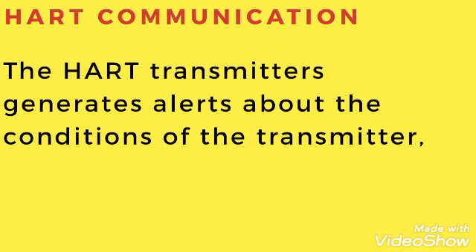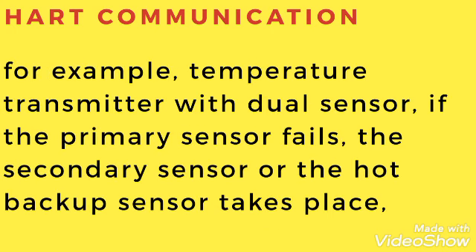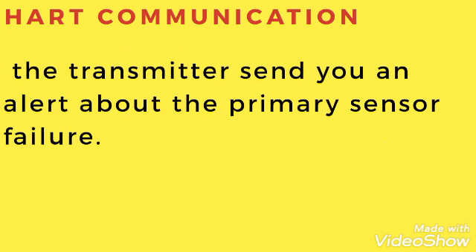The HART transmitter generates alerts about the condition of the transmitter. For example, a temperature transmitter with a dual sensor: if the primary sensor fails, the secondary or hot backup sensor takes over, and the transmitter sends an alert about the primary sensor failure. So we can diagnose faults using the HART communicator.